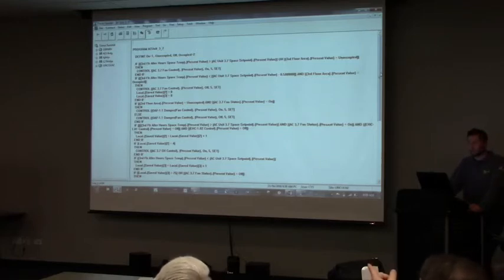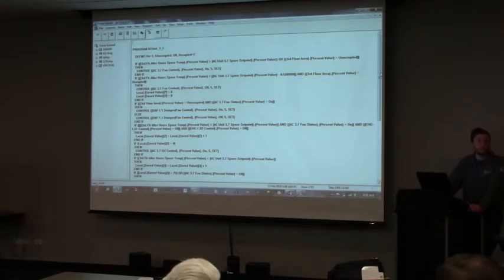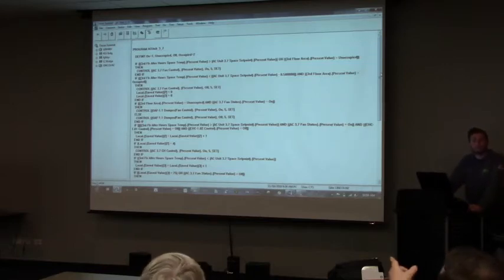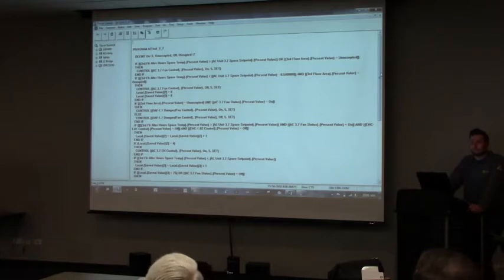So if you see control AC37 fan control, comma, present value, comma, on, and so on, you're passing a list of variables to the control function. That's what the comma is doing. The period is actually representing property. So you're taking a property of a property of a property. In other languages, I don't think you do it in CPL, but you could drill even farther one way or the other by putting more periods with more properties and keep going like that.